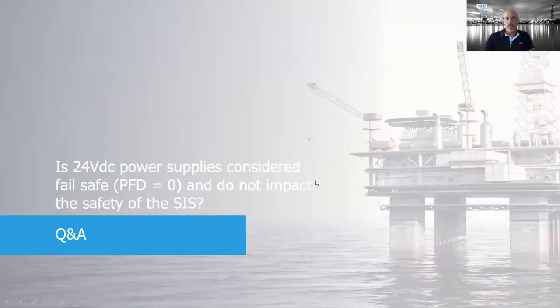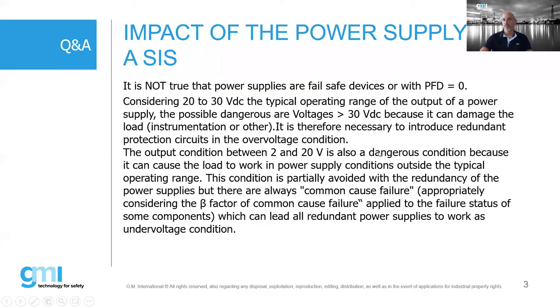So the question was, maybe you can answer this question, Massimo. I tried to answer the question in the meantime while you presented. Yeah, 24 volt, we can repeat it if you like, because it's a very important point. 24 volt DC power supplies considered fail safe, PFD equal to zero, and do not impact the safety of the SIS. So as Massimo said, of course, that's not true, because power supplies are fail safe devices with PFD equal to zero is not true.